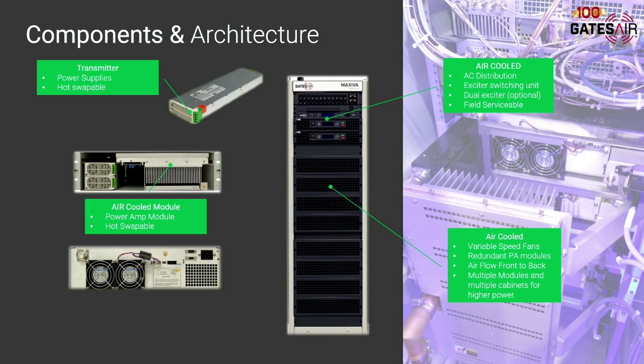So air-cooled modules, you can see that there's an air-cooled module there. And then redundant fans. Whenever you do an air-cooled system, you really want to have redundant fans, because fans are a moving part. They're always going. We use variable speed fans, but you always want a redundant one, so that if something happens to that fan, you have time to take it off and put another one on. You want to be able to do it with the transmitter running, so you want to be able to hot swap that fan out. Well, the new designs of transmitters are designed exactly that way, especially for the air-cooled.